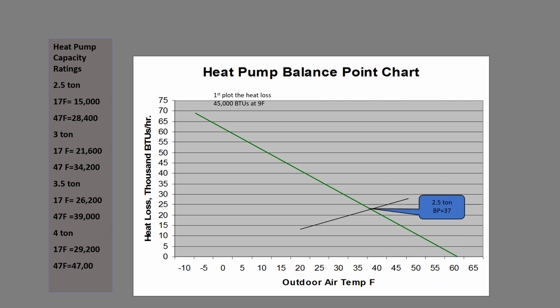Let's plot our 2.5-ton system. So there's our capacity. We've simply drawn a line between capacity at 17 degrees and the capacity at 47 degrees. In this case, that 2.5-ton system would have a balance point of roughly 37 degrees. Too high for our wants.